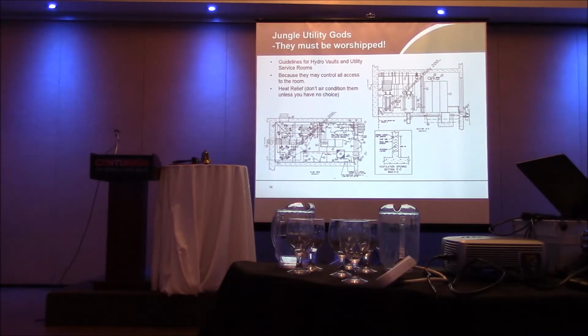If you don't have to, don't air condition the room, just use outside air. Honestly, heavy electrical equipment like this works just fine up to 40 degrees C. It's designed to work at temperatures like that. We don't want to go beyond 40 degrees C because then we have to derate the equipment, but the standard is that it's built and designed to operate up to 40 degrees C without derating.